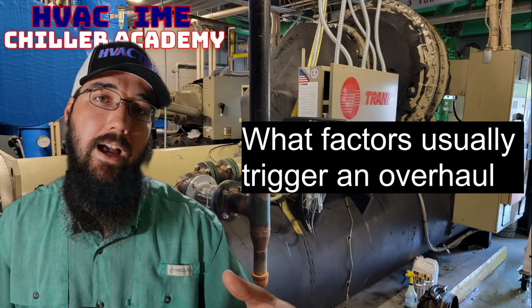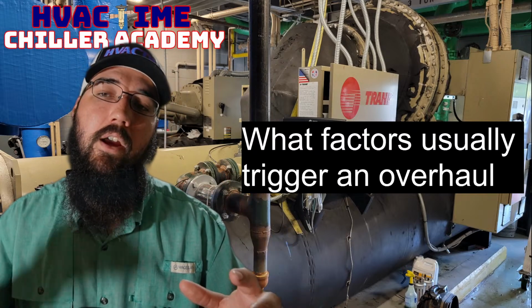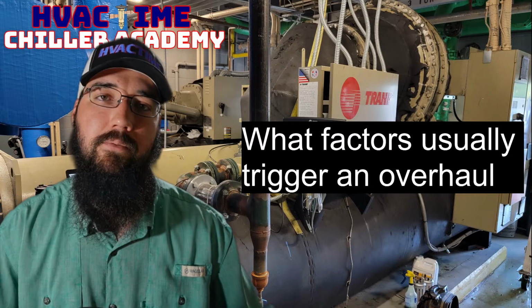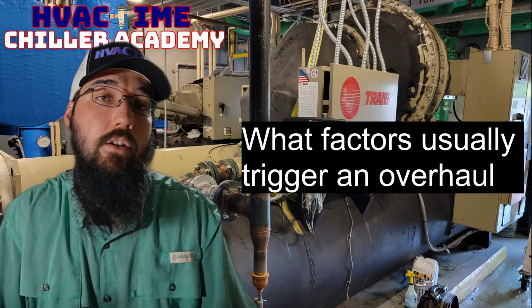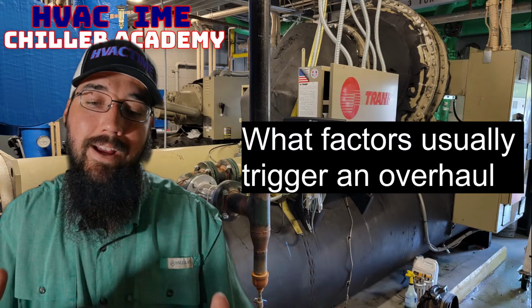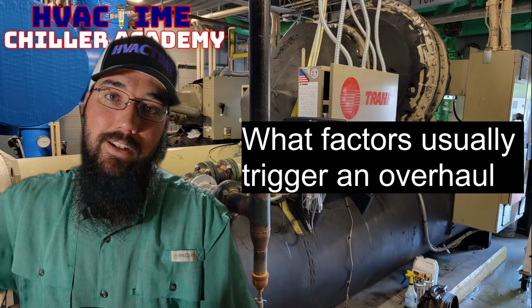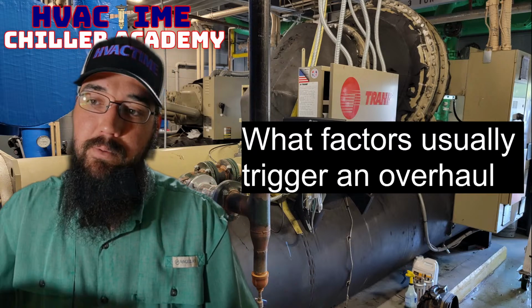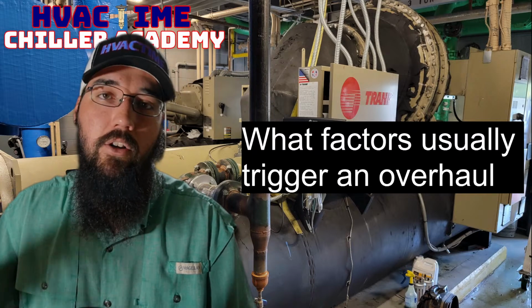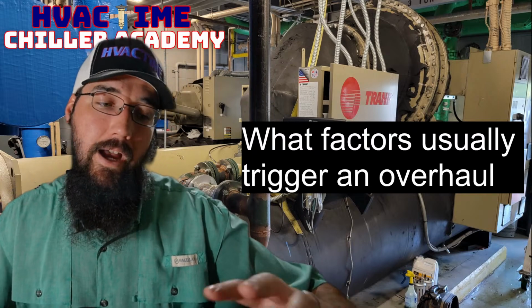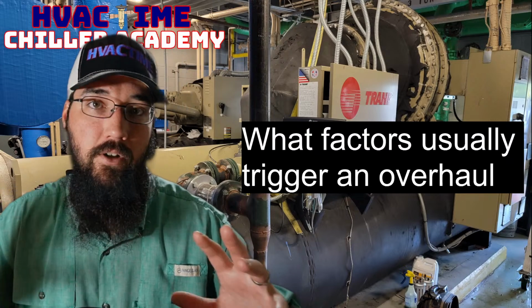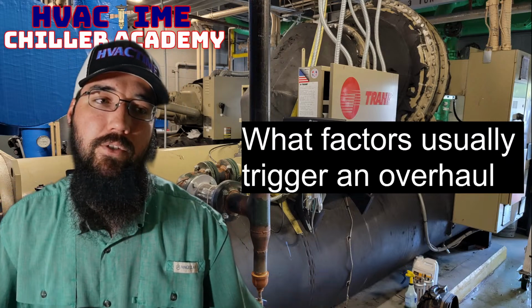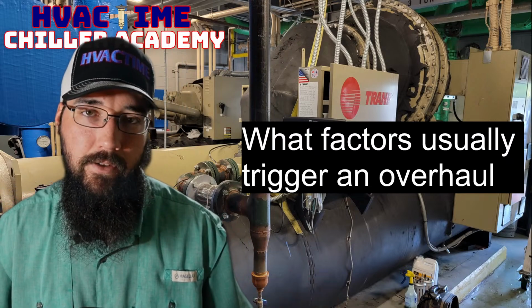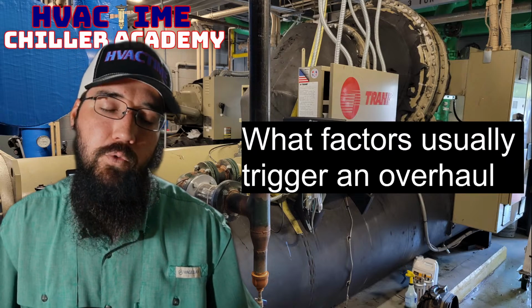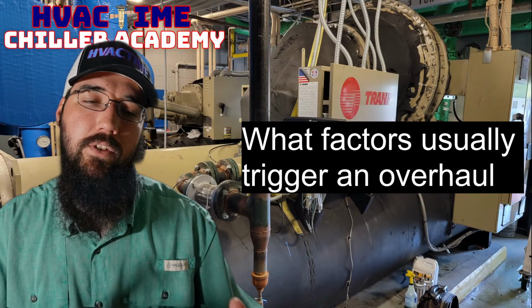We could have an eye seal issue, a labyrinth seal, where we're bypassing the high side directly into the low side. All of those conditions where the compressor, while technically it should be loading up, say we're on a variable speed, but we're at our 60 hertz, or all of those factors are true. IGVs are open, impellers open, all these are true, but yet somehow the compressor ain't compressing. Those would be conditions that would make you say, okay, well, something has happened.